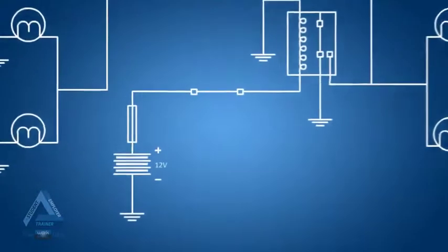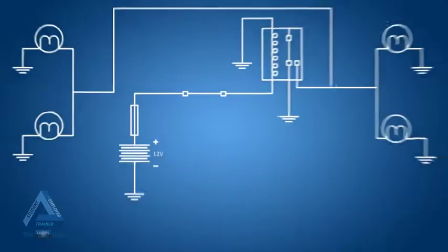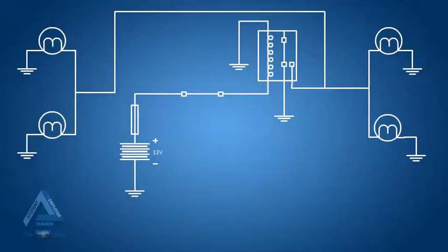The first thing to check is the fuse. If the fuse has tripped, we would need to inspect the rest of the circuit as it is likely there would be a short occurring somewhere in the system. However, in this case, the fuse is fine.